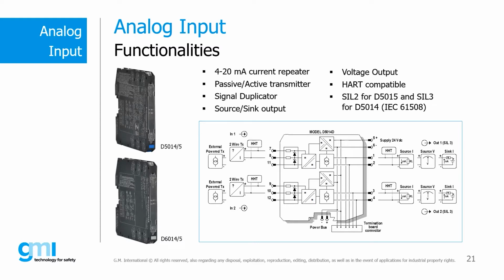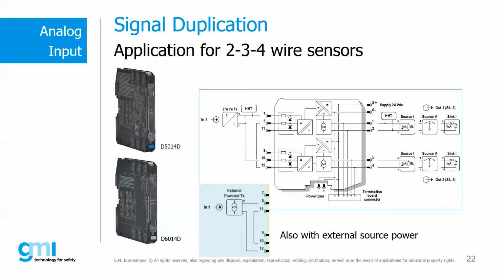That is, let's say, generated by the system or by an auxiliary power supply. It can have voltage output, and what we are offering is SIL2 and SIL3 certification in different situations. We can also have the same unit or another unit used for duplication. In this case, you have one input generated from a field device, and the output can be retransmitted to the system or to two systems, two inputs probably from your system, also with different standards, milliamps and also volts. In this case you retransmit two different signals, so probably used for redundancy applications.